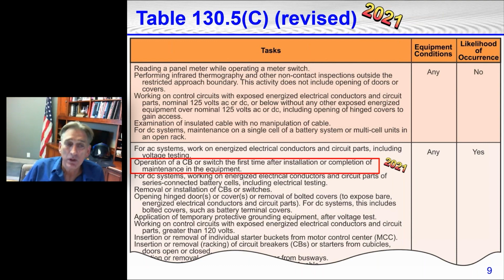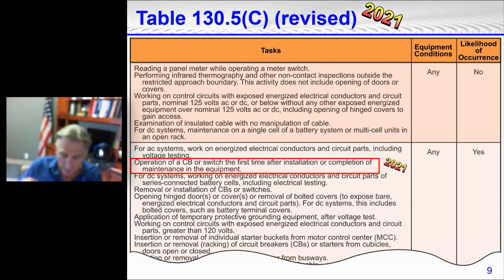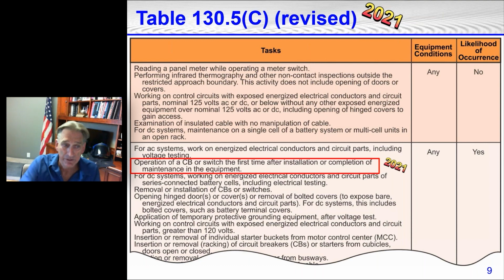For AC systems, work on energized electrical conductors and circuit parts, including voltage testing. We'll come back to this one in a few minutes. The second line item in that second block there is new to the 2021 edition. It says operation of a circuit breaker or switch the first time after installation or completion of maintenance in the equipment. All right, so you install a brand new panel board. The first time you turn it on, you see, okay, well, let's see, that line says operation of a circuit breaker or switch first time after installation.